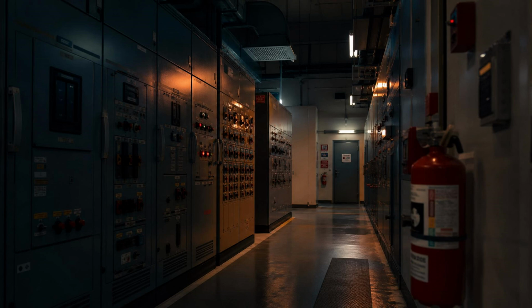When the exercise period is complete, the generator is allowed to cool down. A brief period of running at reduced or no load before the engine is shut down, allowing the cooling system to carry excess heat away from the engine before it goes still again. Then the shutdown. The engine decelerates. The sound decreases from its steady operational note through the lower registers of deceleration and then, finally, to silence. The room is quiet again. The generator rests, and the technician notes the exercise time, the performance readings, and the result, satisfactory, on the clipboard.